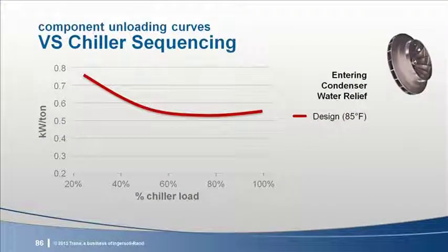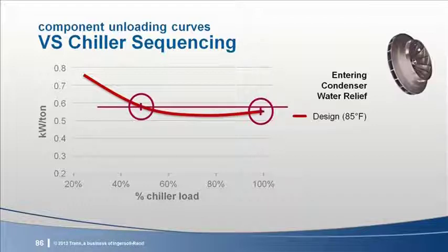Here again is the design condenser water temperature unloading curve. If one chiller is running at full load, it will draw approximately 0.55 kW per ton. If at the same condenser water condition we turned on a second chiller and shared the system load so that 2 chillers are each running at 50% load, they would run at a less efficient 0.58 kW per ton.